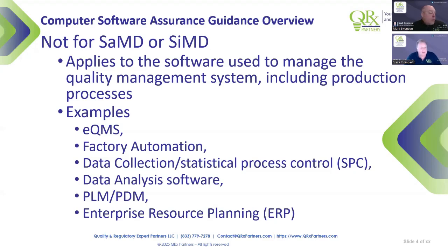And I said could, right? And it's not a guarantee. Data analysis software, potentially. Product lifecycle management, product data management systems, almost definitely fit as part of your quality system. And then ERP, and we'll talk more about that one because that one does get missed as people think, well, that's just a business management system. But there are elements usually in your ERP that become part of your required record keeping from a regulatory perspective. And so, therefore, parts of your ERP system could definitely need application of this guidance.